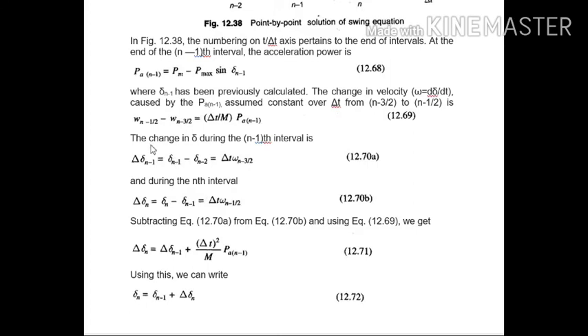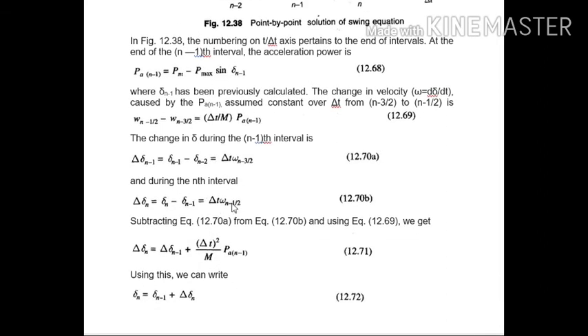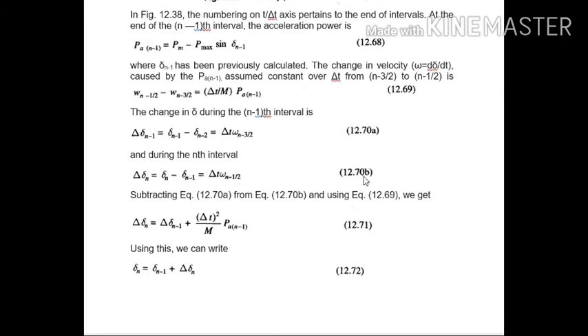Our actual goal is to calculate the change in rotor angle δ for a very small interval of time, so that we can plot the swing curve (δ versus t). We can write Δδ(n−1) = Δt · ω(n−3/2), and similarly Δδ(n) = Δt · ω(n−1/2) (equations 12.70a and 12.70b). Subtracting equation 12.70a from 12.70b and using equation 12.69, we get the key recurrence relation. Substituting all values gives the final expression: δ(n) = δ(n−1) + Δδ(n).